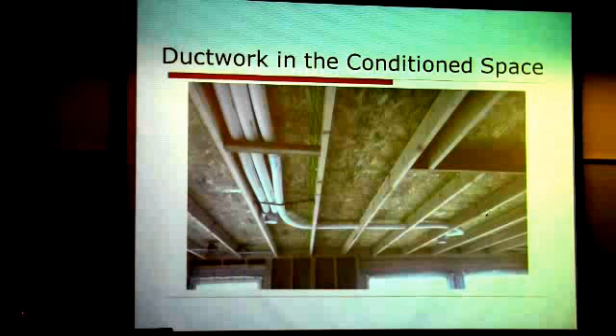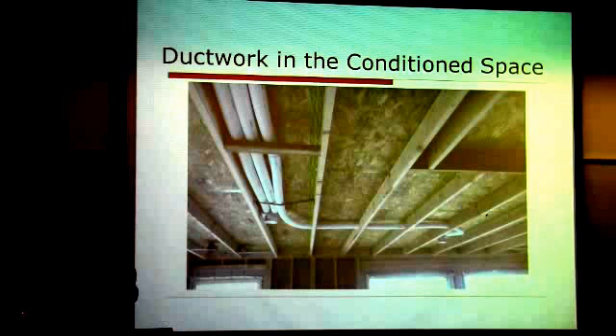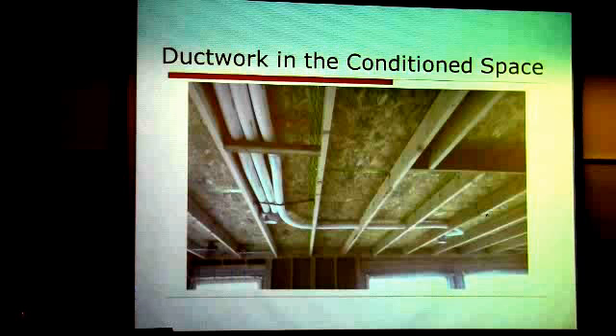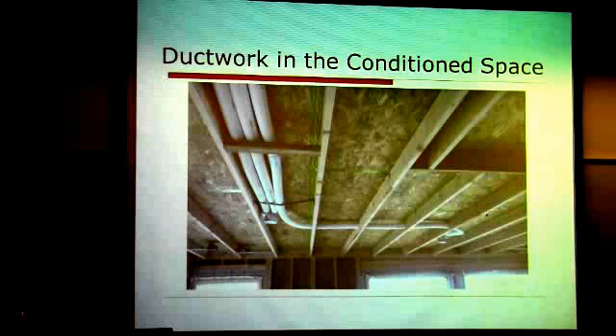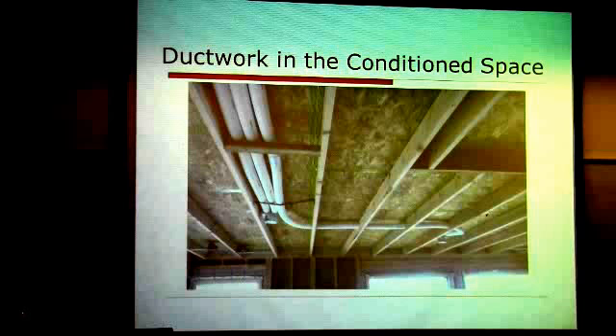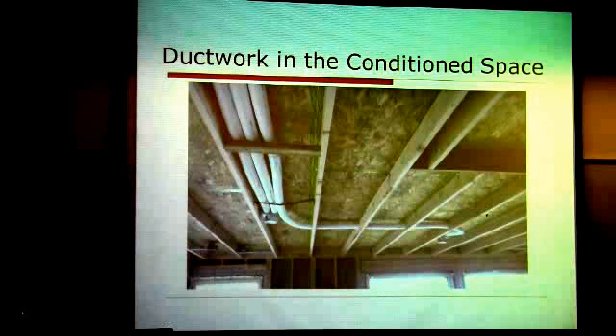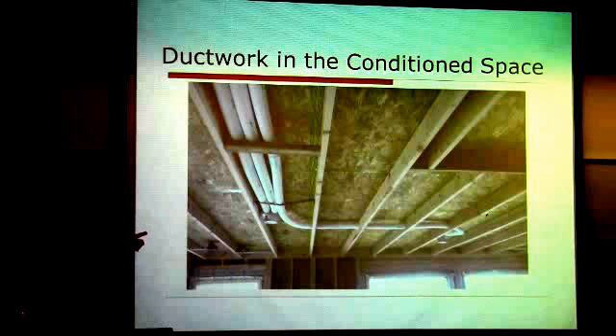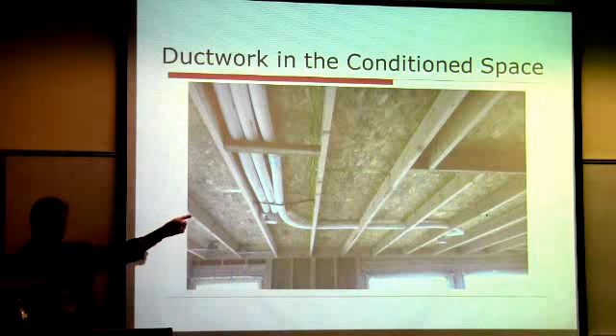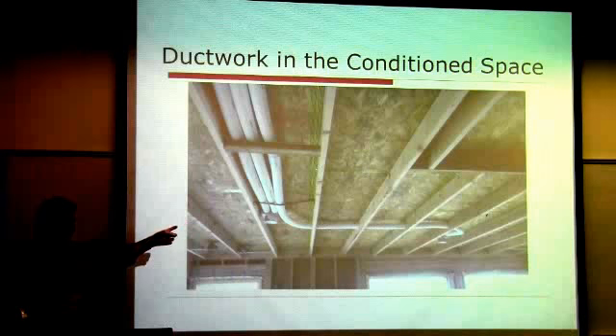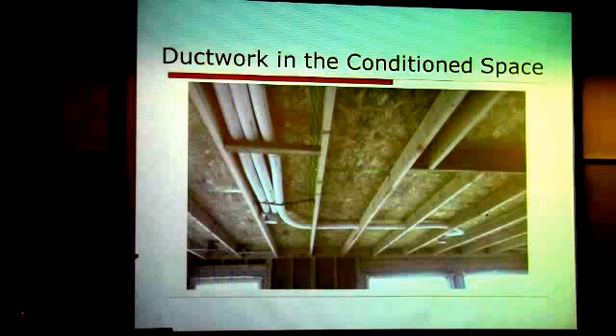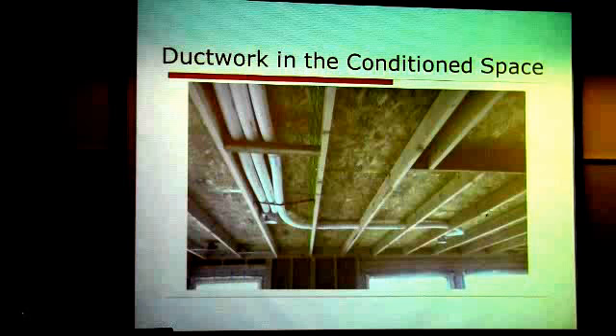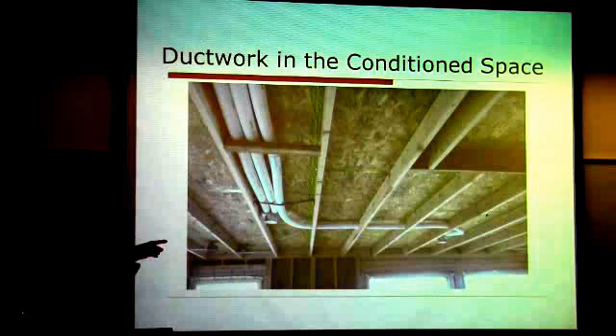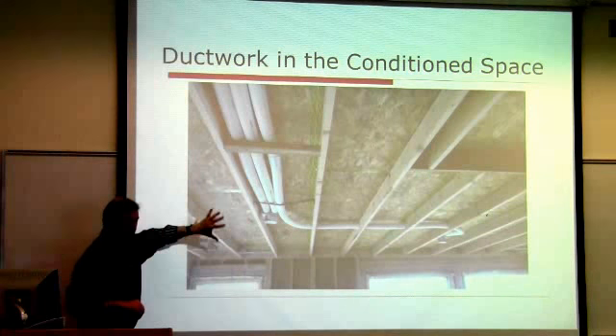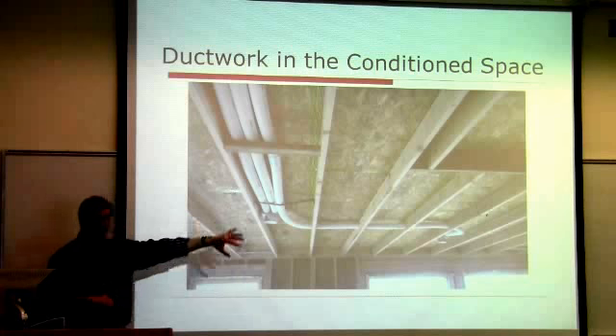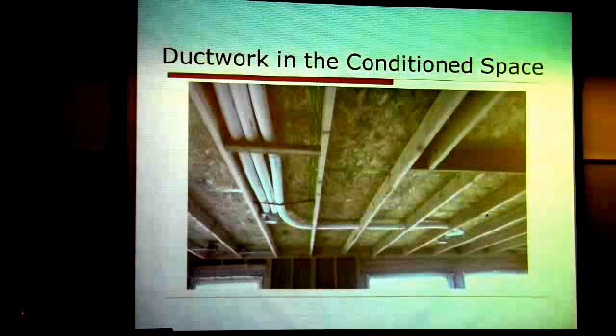This shows you want the ductwork, like we talked about, kept in the conditioned space. Before, this ductwork probably would have gone in the attic, but on a passive house and high-performance homes, you want to keep all the heating system inside, so any losses from it stay in the house and you're not going into unconditioned attics. And this construction shows that they put OSB on the bottom of the trusses as their ceiling barrier. Normally you just put drywall up there, tape it, call it good, but you really can't seal that perfectly. So they took OSB sheets, put them on, and then actually had a drop ceiling for all the electrical work and lights.